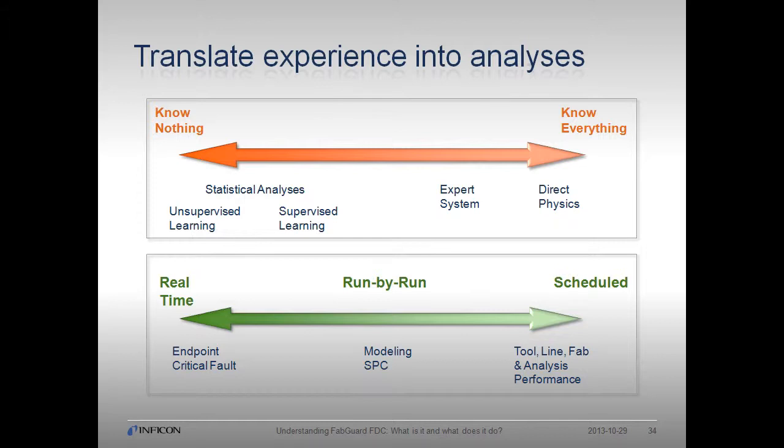Think of the expert system as a way to automate failure mode and effect analysis entries. For example, a wafer will be damaged by charging if there are too many interruptions during an implant process, and expert system rules can be put in place to notify the engineer and/or perform an action on the equipment. At the far end, where we know everything about the process — the direct physics — FabGuard can also be implemented using expert system rules and advanced modeling techniques. For example, implant analyzer magnet health can be accurately modeled using direct physics to indicate whether the calibration has shifted, resulting in the wrong species being implanted into product.